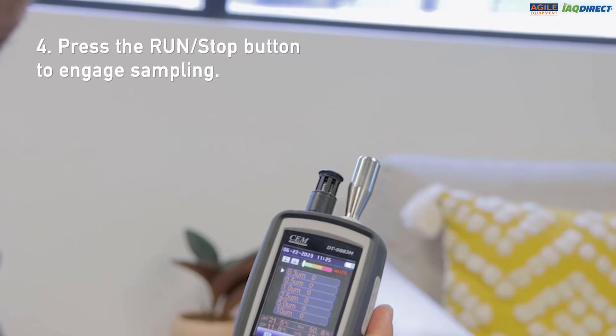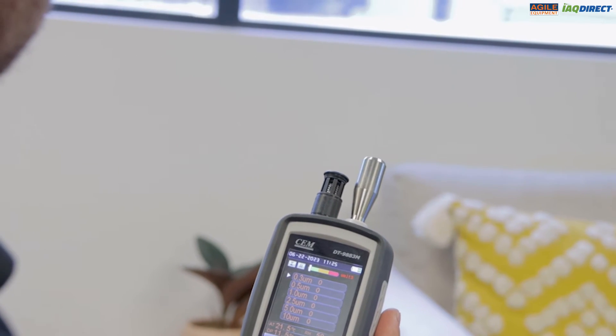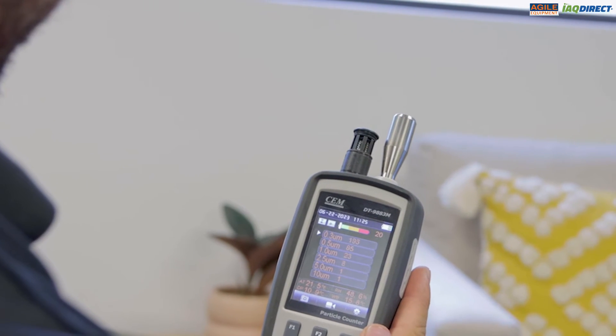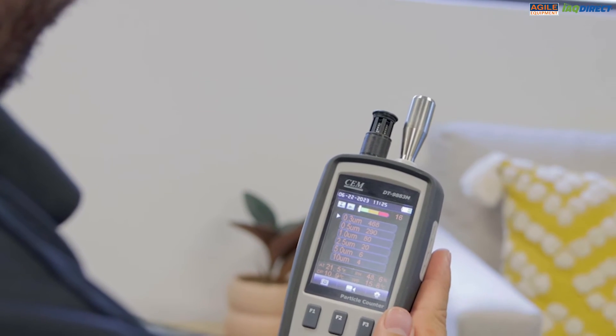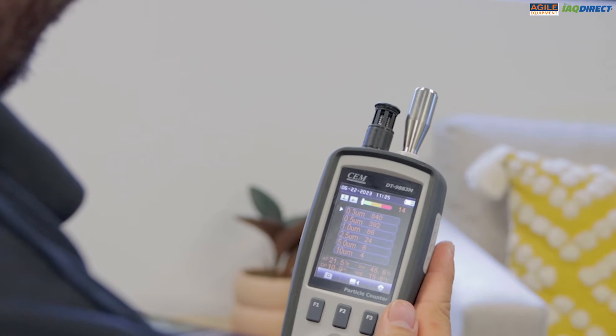Press the run stop button to engage sampling. As you can see, the meter starts counting in six different channels, from 0.3 microns all the way up to 10 microns.